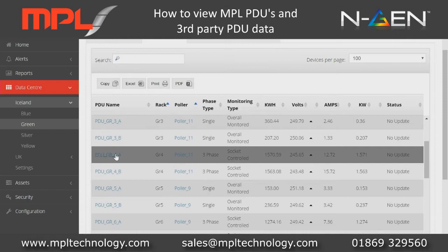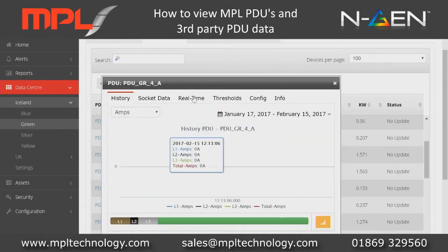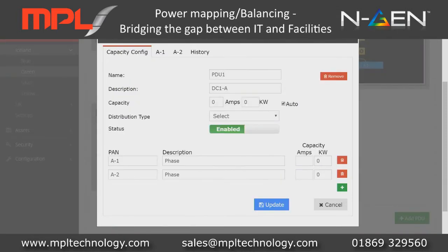If we click on a particular tap-off, just like we do with the PDU, again, you can analyze everything in a similar fashion. One of the key features here in enabling the correct capacity management in the PDU breaker is that we can auto-calculate the amps and the kilowatts. So if we put into the amps field, for example, 100 amps, this will auto-calculate the kilowatts. This is a very useful feature for any user to avoid having to calculate kilowatts independently.